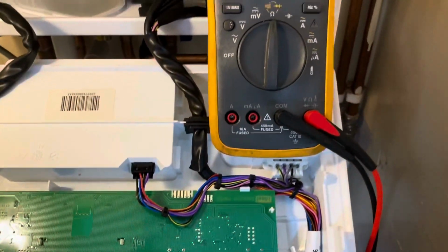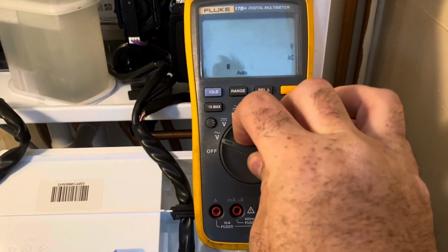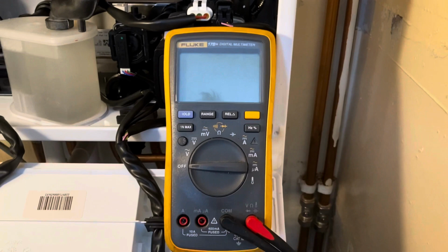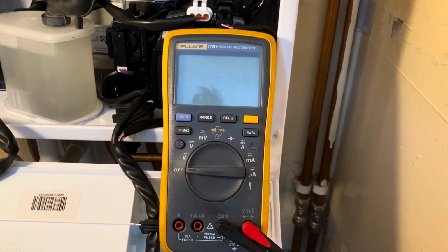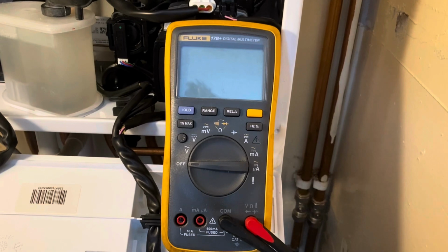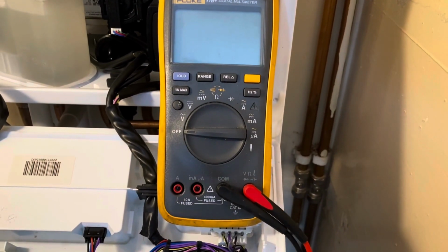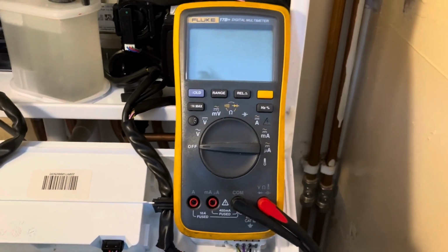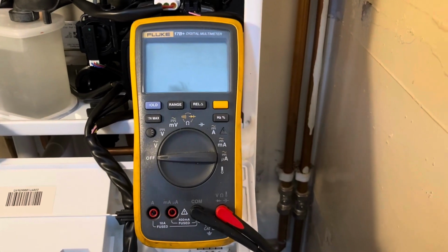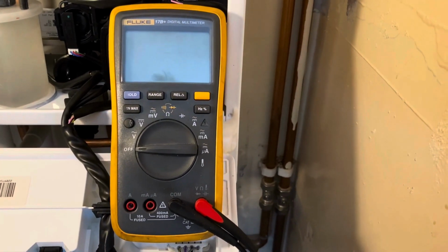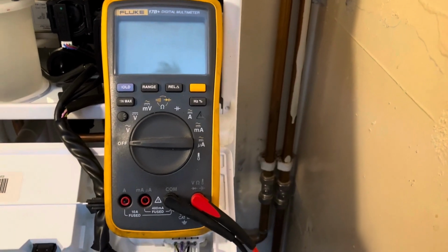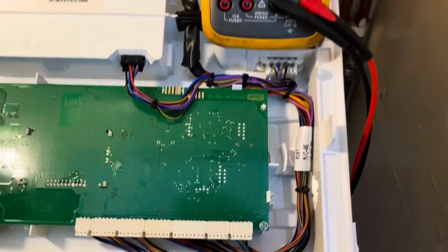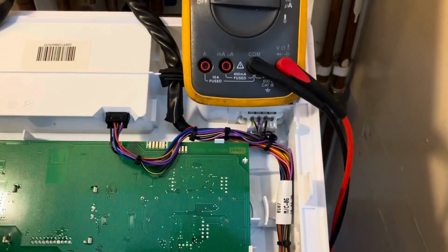With thermistors, they are a thermostat resistor, so obviously with the temperature change, the resistance changes through the component, so therefore the current flowing through it changes, and which will change the amount of voltage that can be pulled through it too. So the low voltage that's flowing through the thermistor will change up and down depending on the temperature and resistance, and therefore the circuit board will see the voltage change, and with the algorithm on the board it will know what temperature that thermistor is at by what voltage it's getting back.